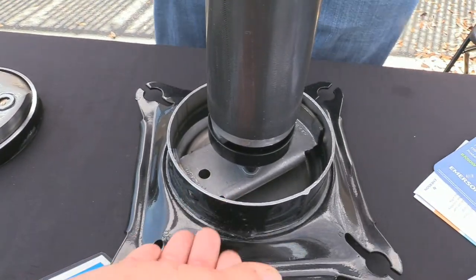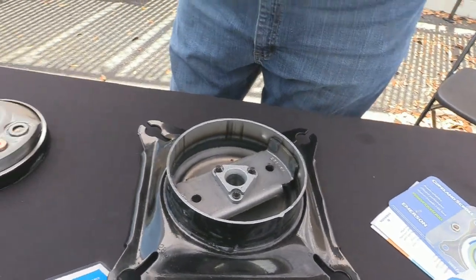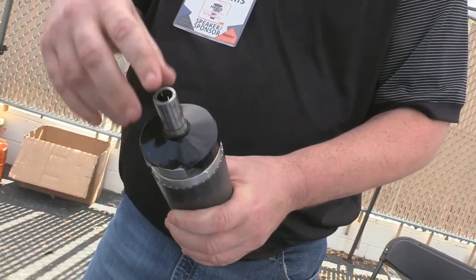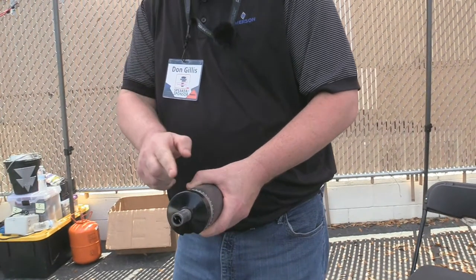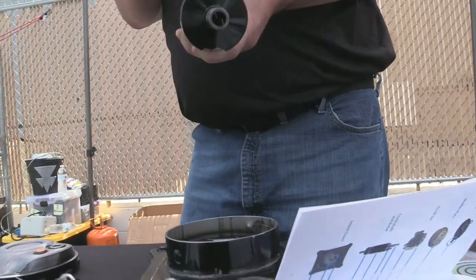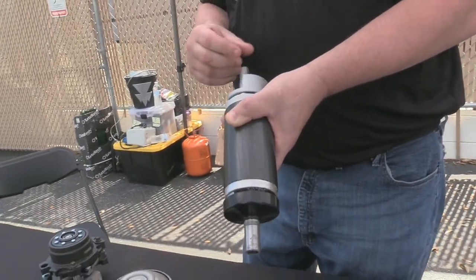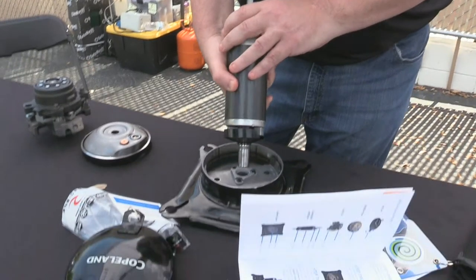It sits down at the bottom where oil collects in the compressor. Notice the size of this hole — it's a lot smaller than the other, which causes a venturi effect on startup. These paddles stir the oil up, almost like a straw. And this hole — if you could see through it — is bored out at a slight angle so that from centrifugal force, the oil goes up almost like a barber pole outside a barbershop.